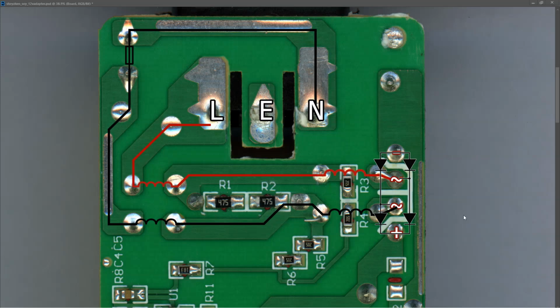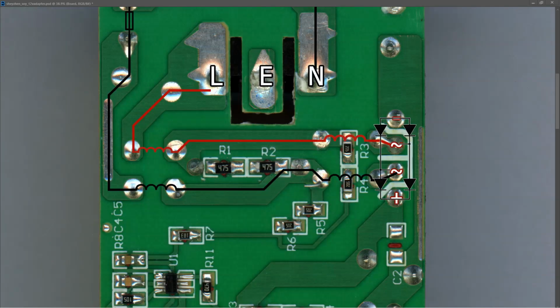Last week I found that the bridge rectifier at this position was shorted, and I replaced it with a good bridge rectifier, and then we observed that the monitor came on and everything was working. But if I didn't have a monitor to test it with, how could I verify that this bridge rectifier is working? The purpose of our bridge rectifier is to convert our mains AC into a high voltage DC, and this is the equation we can use for calculating it.